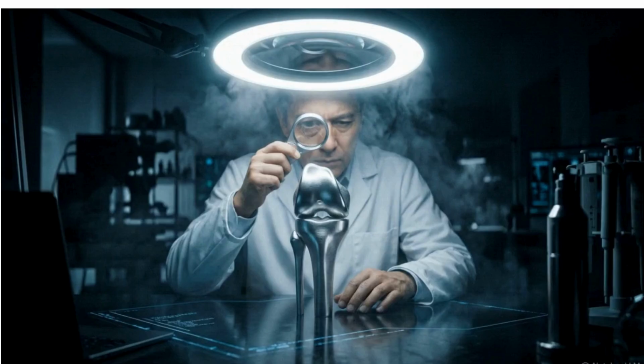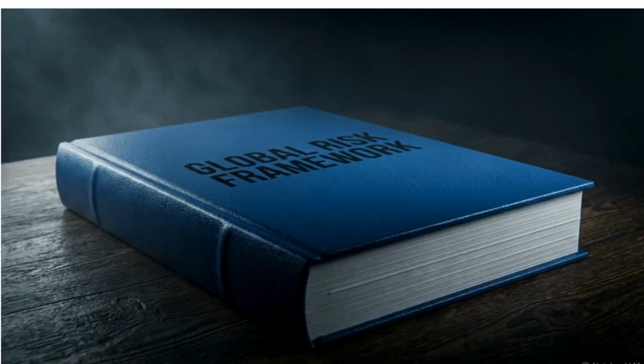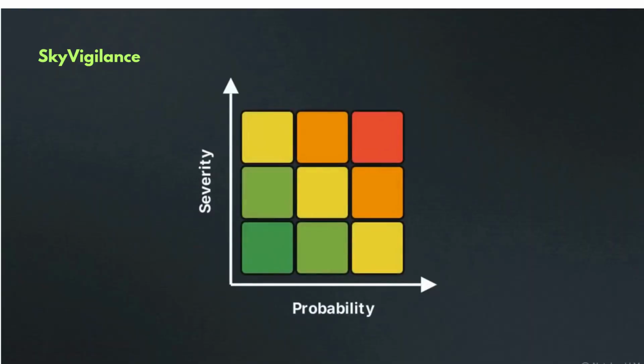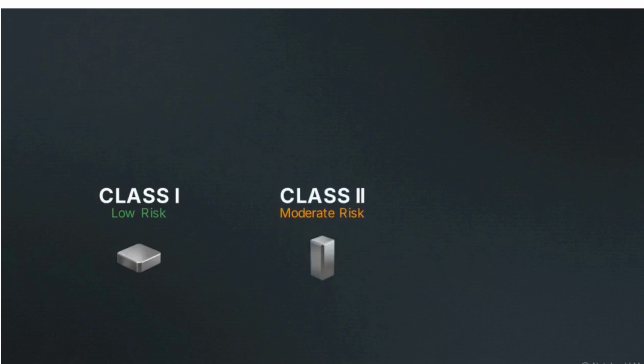Before any of that monitoring can happen, manufacturers must determine how dangerous their product might be. Globally, this is governed by a framework known as ISO 14971, the International Standard for Medical Device Risk Management. This matrix visualizes risk calculation. You multiply the probability of a harm occurring by the severity of that potential harm. This dictates regulatory classification, scaling upward from low-risk Class 1 to moderate Class 2 to high-risk Class 3.